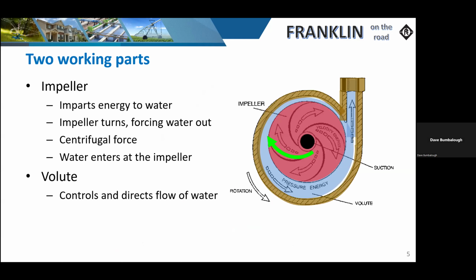So the two main working parts of a pump are the impeller and what is referred to as the volute, or in most cases called the bowl. The impeller is the moving portion. It's what's connected directly to the shaft of the motor. So in our case, the electric motor is going to spin that impeller. Now, it is directional. It does need to be spun in the right direction to make sure that the flow of water is correct, so we're able to build pressure and move that volume of water.